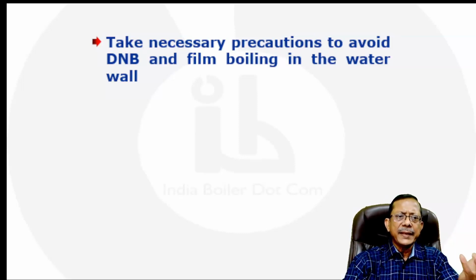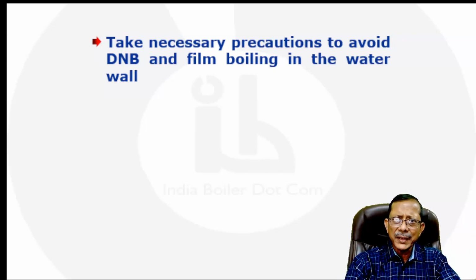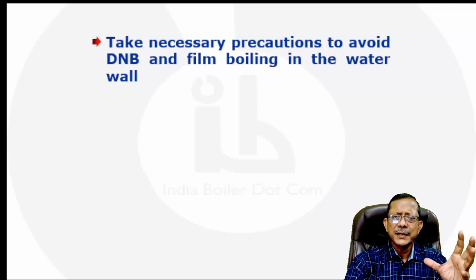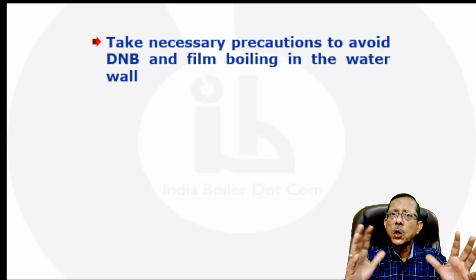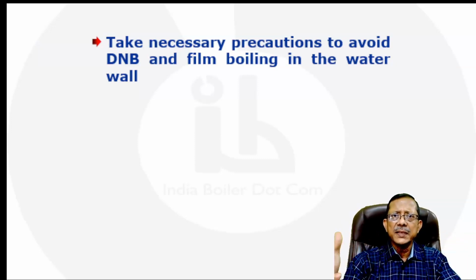And suppose you find an indication that lots of deposits have formed in the boiler system, right? It can be found out during one of the failures, if you go for looking inside the component and find some deposits, right? It gives you an indication that the boiler is becoming dirty. And particularly if the deposit analysis shows that there is some conductive metallurgy like copper or brass getting deposited there, see, these are highly conductive and it creates a strong galvanic cell. And wherever there is a galvanic cell, there is a possibility of corrosion and subsequent deposits. These deposits will again lead to the further problem of under deposit boiling, wick boiling that is called, and further corrosion.